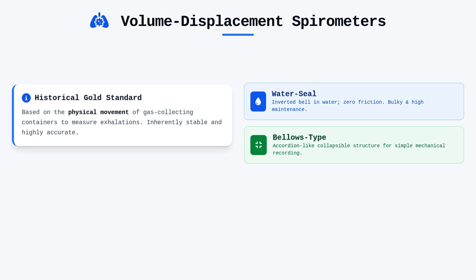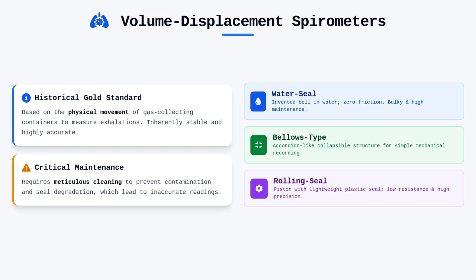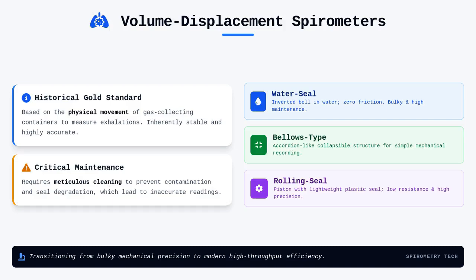Bellows-type spirometers use a collapsible, accordion-like structure that expands as volume is added, providing a simple mechanical method to record displacement. The rolling seal spirometer improves upon this by using a piston paired with a lightweight plastic seal, providing low resistance while maintaining high precision. These displacement designs are inherently stable, but they require meticulous cleaning to prevent contamination or seal degradation that could otherwise lead to inaccurate volume readings.